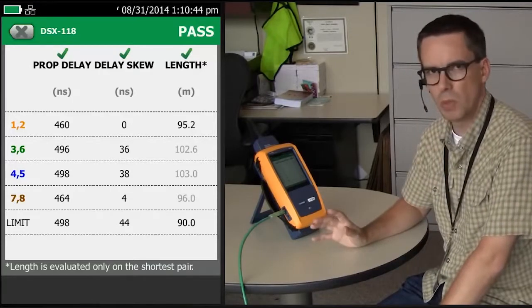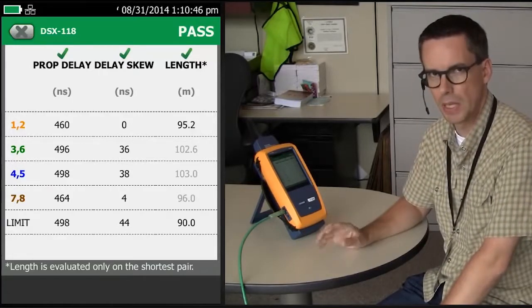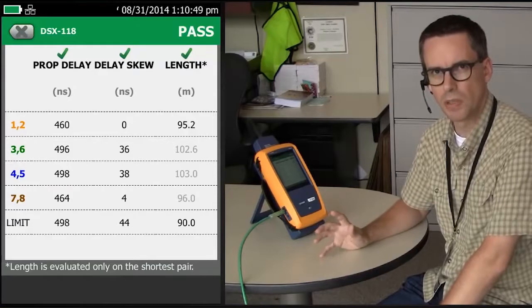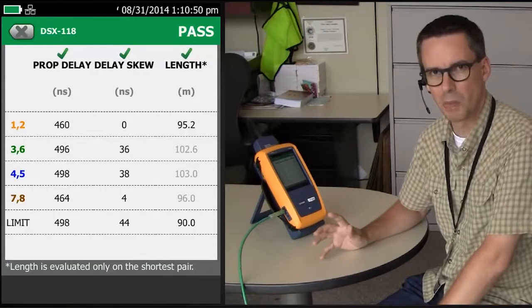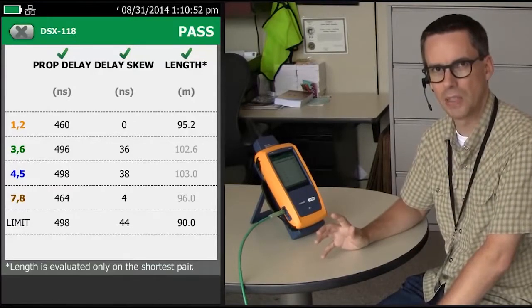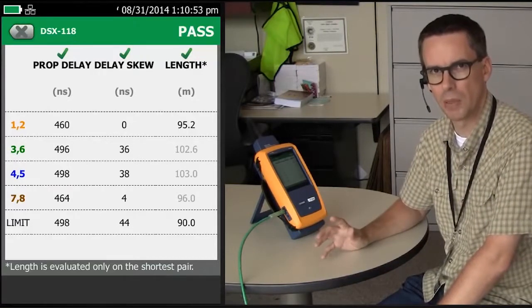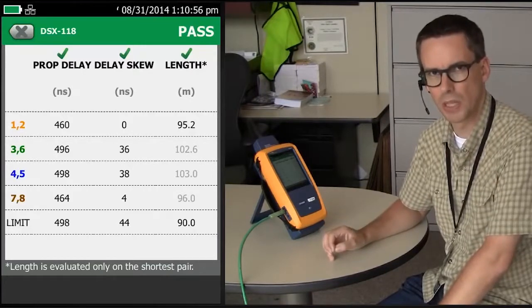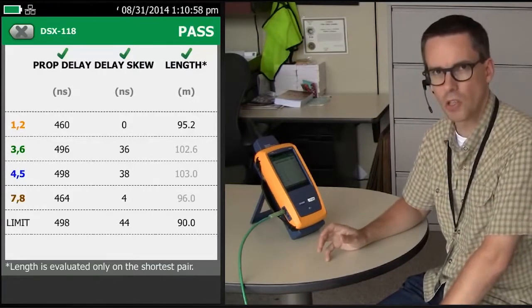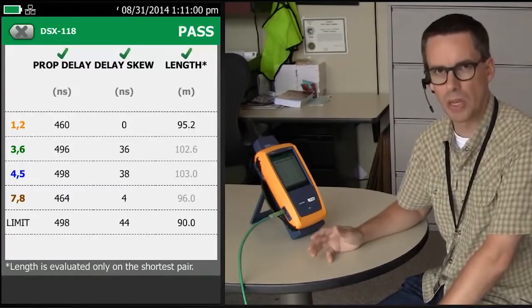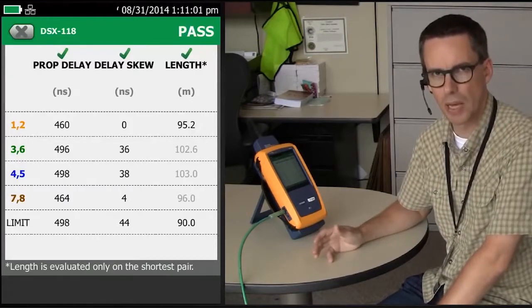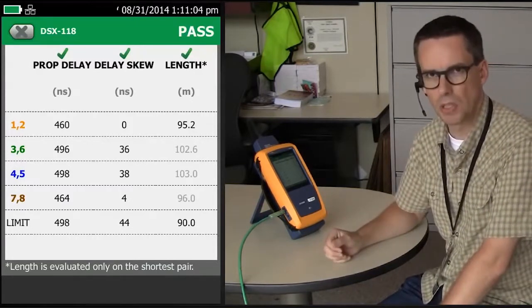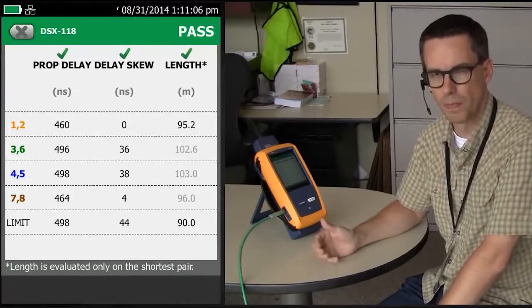Now, people normally get really wound up about this, but here's the reality. The active equipment doesn't care so much about the length. What it cares about is the length-dependent parameters — insertion loss and propagation delay. So if the insertion loss passes and the propagation delay passes, who really cares whether it's 95 meters or not?